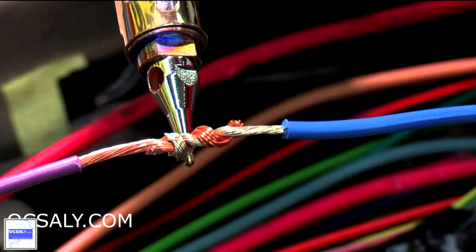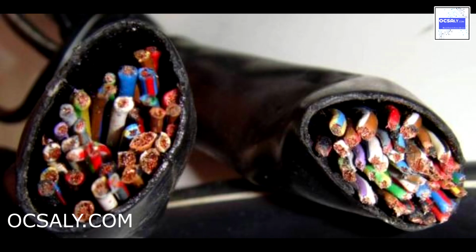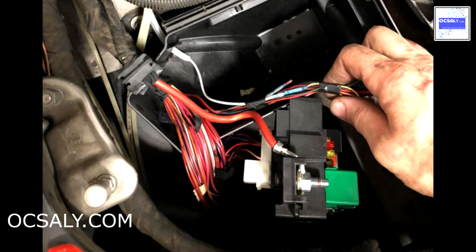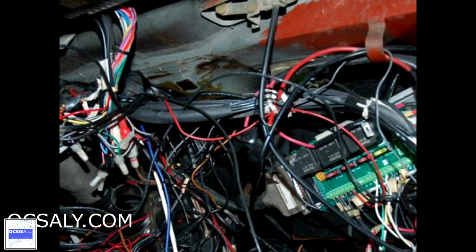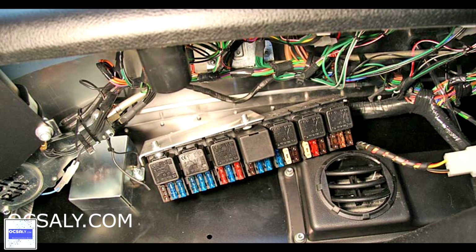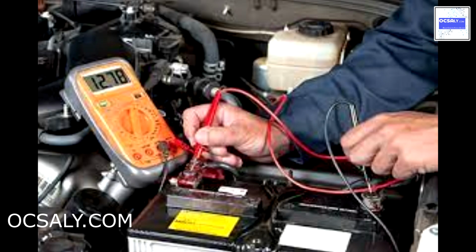The sort of repair employed will be determined by a variety of criteria, including: 1. Type of repair required. 2. Ease of access to the damaged area. 3. Type of conductor. 4. Size of wire. 5. Circuit requirements. 6. Manufacturer's recommendations. Wrapping damaged insulation with wire is one of the most popular ways of wire restoration. Other methods include soldering, crimping the connections with solderless connectors, and electrical tape or tubing splices.